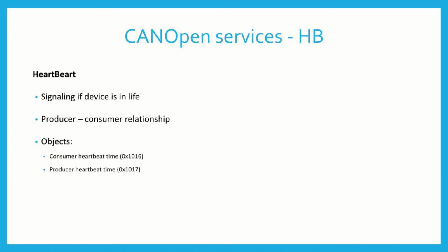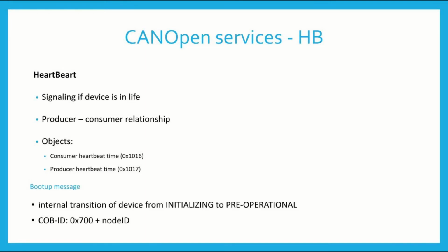A heartbeat service is used to detect if the device is in service. A device could be a heartbeat producer, which is typical for end devices like position encoders or sensors, or a consumer, or both. A boot-up message is a message that is sent by a device when it switches itself from the initializing state to the pre-operational state. It has the COB-ID 700 hex plus node ID. Thus, the device signals that it is prepared to be switched to the operational mode.